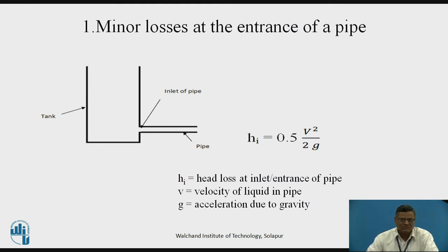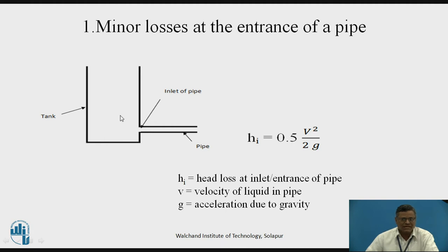Let us see one by one the different types of losses. The first one is the minor losses at the entrance of a pipe. We can see that here we have a tank and the pipe is connected to it. This section is where the pipe is connected to the tank — the entrance or inlet of a pipe. The loss at the entrance is given by the formula: head loss at inlet equals 0.5 × V²/2g, where V is the velocity of the liquid in the pipe. The velocity of the liquid in the tank is zero, so when it enters the pipe, the fluid particles gain velocity and that pipe velocity is used for the calculation.